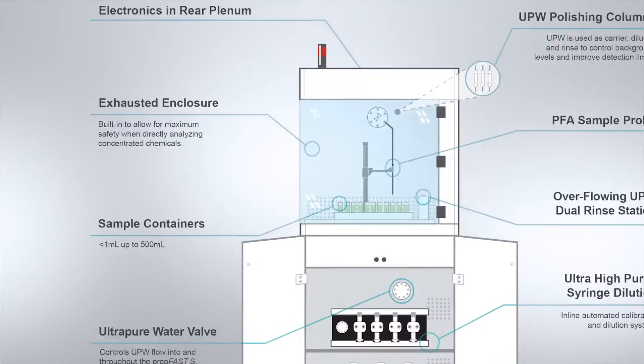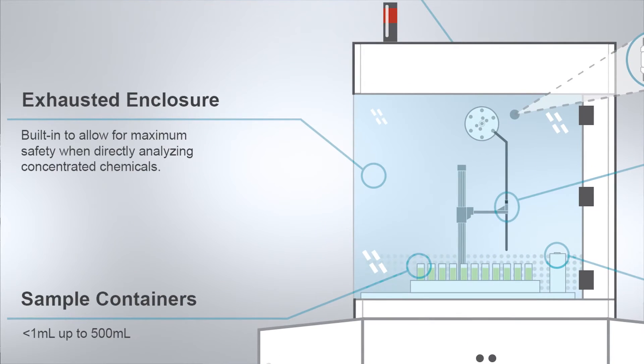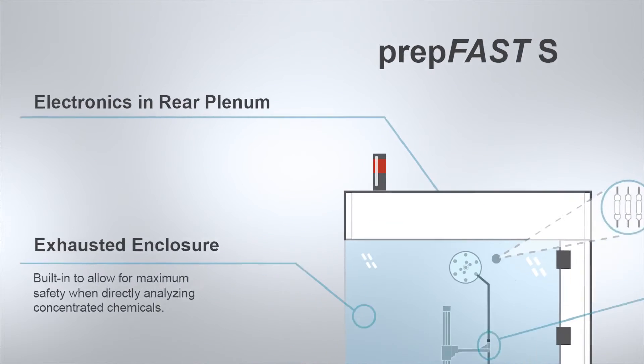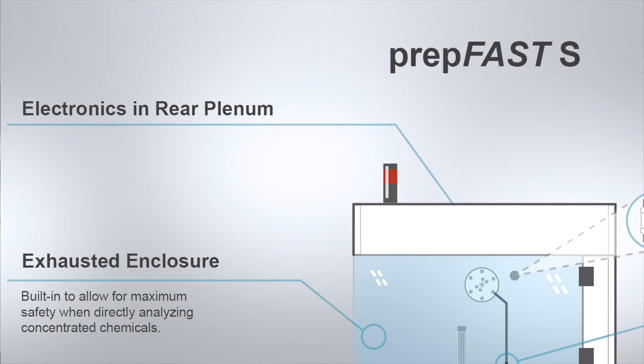It starts with an enclosed and exhausted auto-sampler deck with optional purge gas to minimize the potential of sample contamination while awaiting analysis, even when not placed in a clean room. All the electronics for the auto-sampler are located in a separated rear plenum.